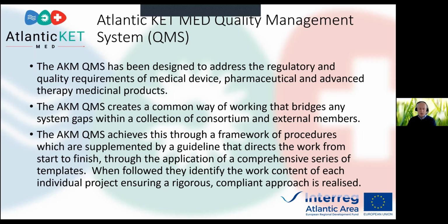The system, though, does embody pharma GMP, which is also applied to the advanced therapy products. By GMP, a really good example of that is the Orange Guide that's produced by the MHRA. The last update was actually done in 2017. I also noted recently that they've updated their risk management guide as well last year. And then the medical device QMS standard, which is ISO standard 13485. If you look across the Atlantic, then that's defined by the Code of Federal Regulations that the FDA apply. And for the devices, the regulations that apply to the medical device aspect are 21 CFR 820.3.